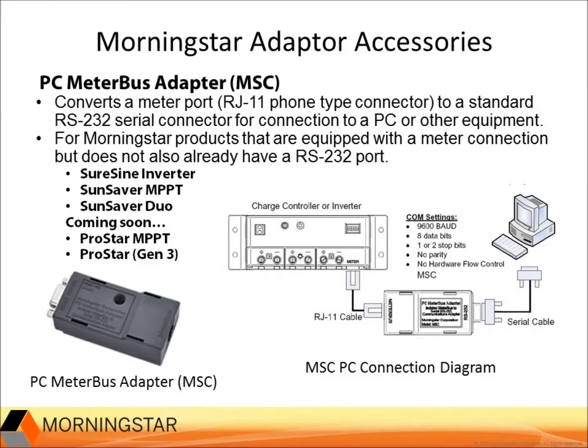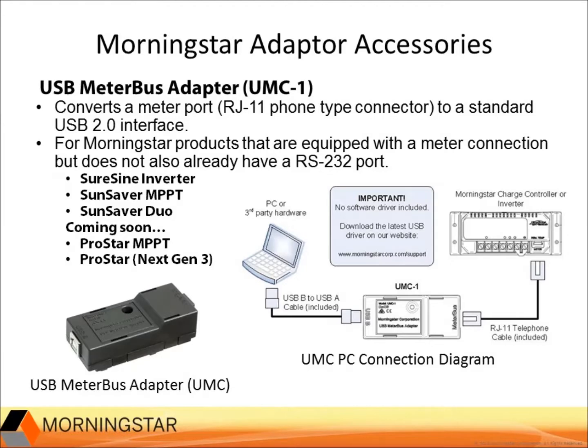One thing to note is that these devices need to be set for Meterbus protocol or Modbus protocol, so they can't be connected to both a meter and have a remote RS-232 connection at the same time. The USB Meterbus adapter is similar to the MSC adapter except that it converts the RJ11 meter port into a USB port for connecting to a PC.